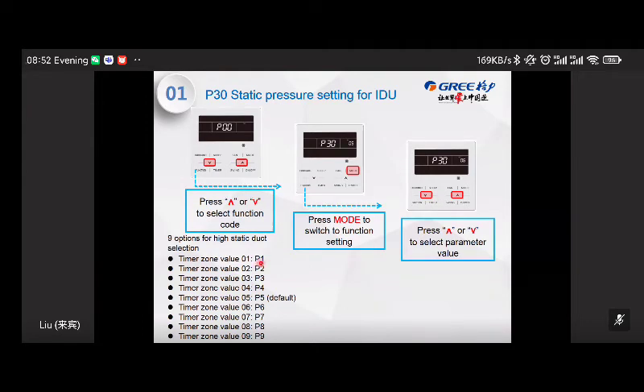You may just lower down the ESP to a smaller value. Okay, and actually P30 is very useful for the VRF, and not only for duct, but also to change the fan speed so that you can make the air conditioning performance better. Yeah, also about the noise complaints, to change the value, to troubleshoot that.